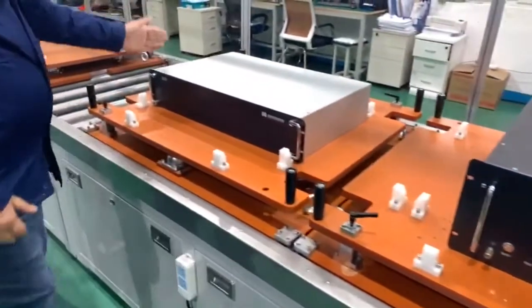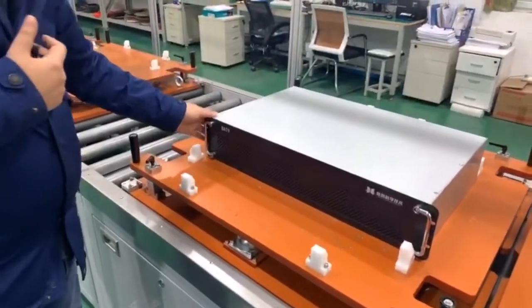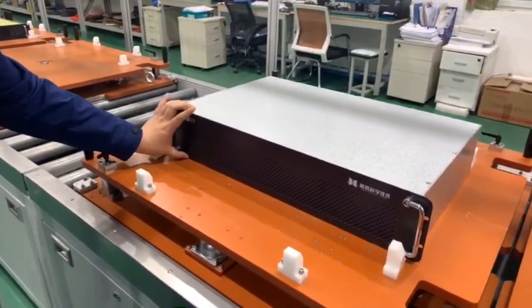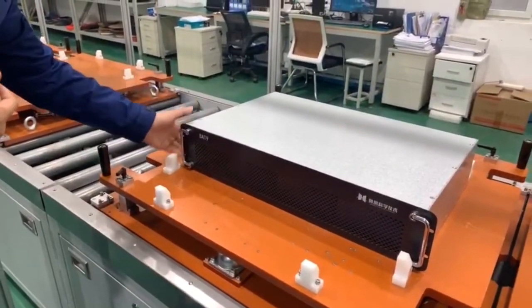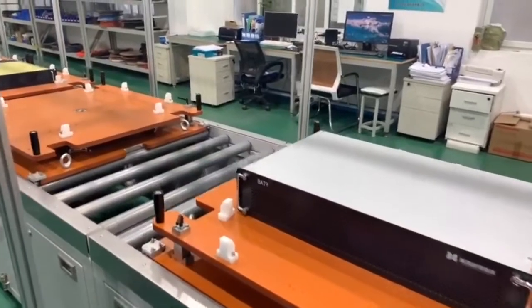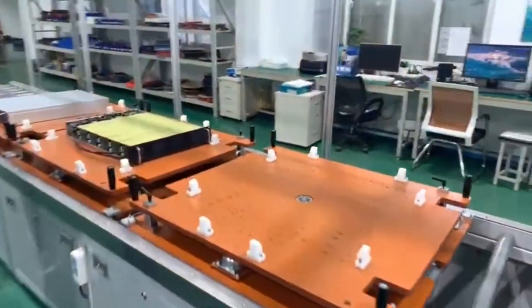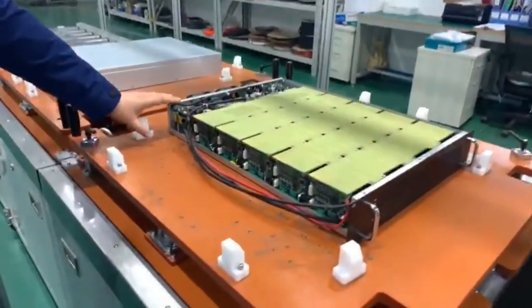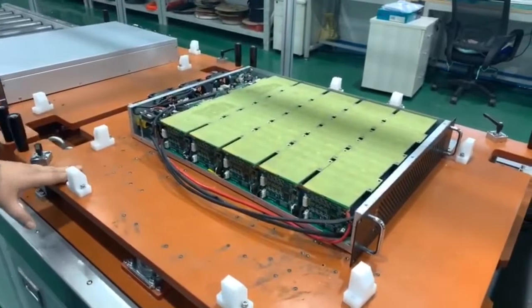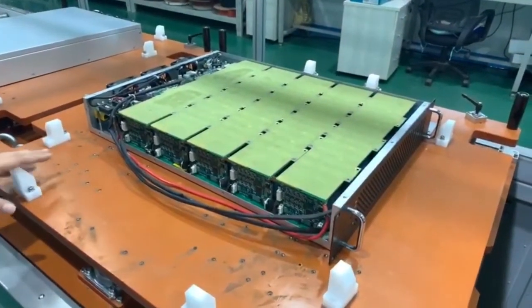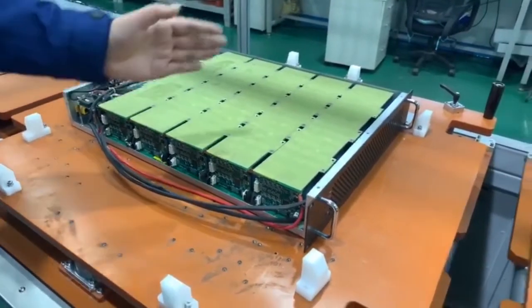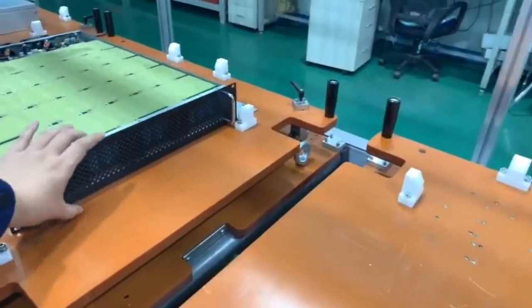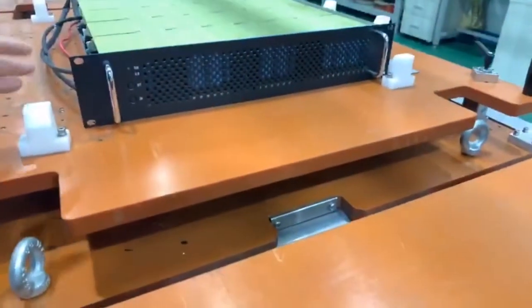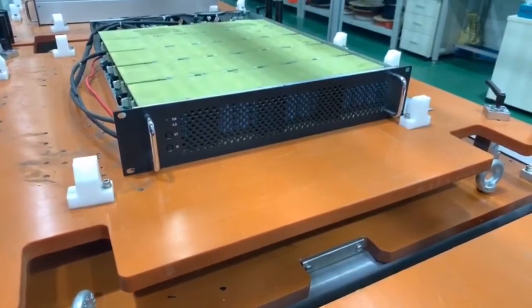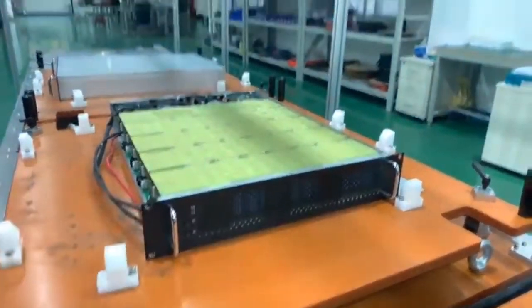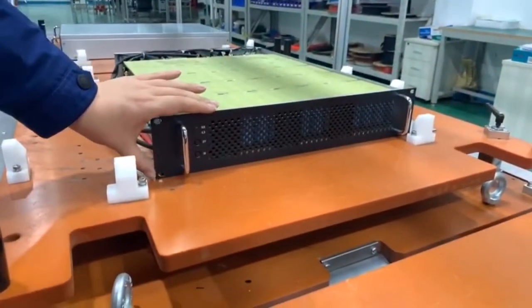Here we have some other different types of lithium battery modules. This one is 3U size with fast charge and fast discharge, 3C discharge. This one is also designed for UPS - 240 volts, 10 ampere hour, with max 3C discharge. The interesting part is this system is only 2U size, and the size is exactly designed for the 19-inch IDC rack, so it's designed for UPS applications.